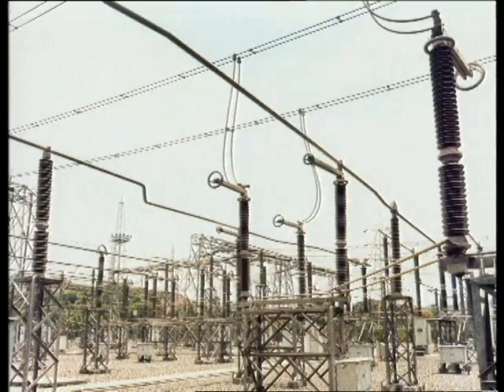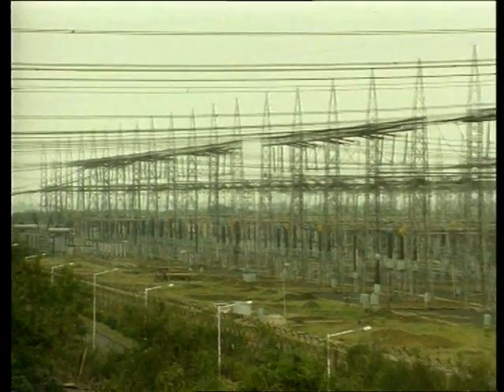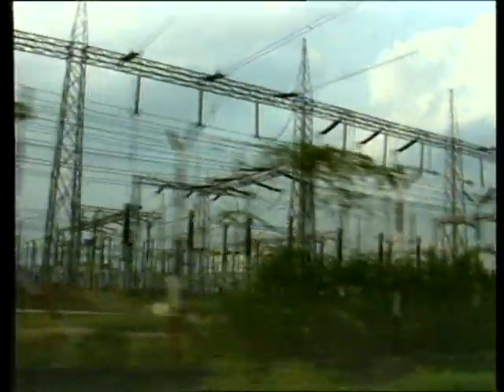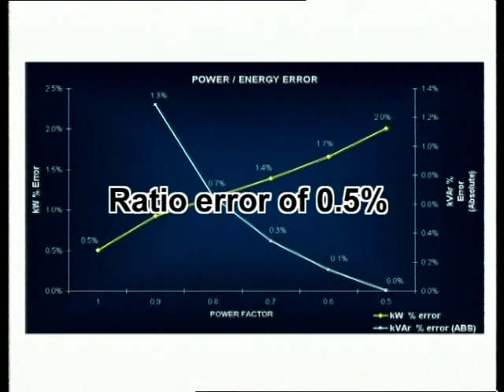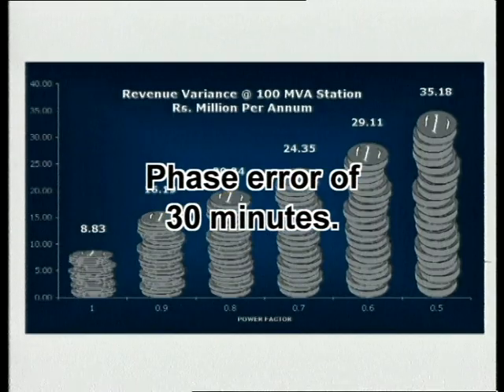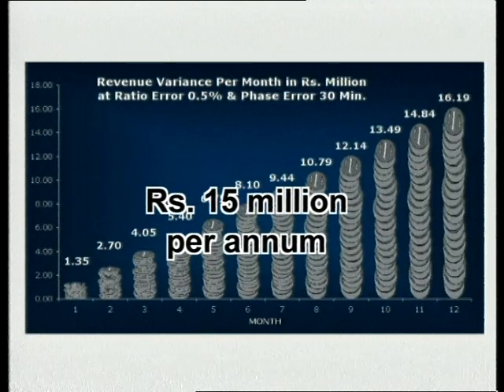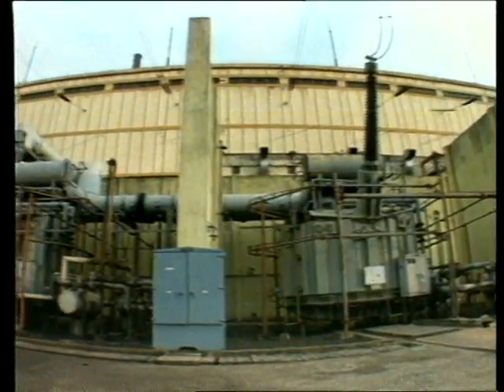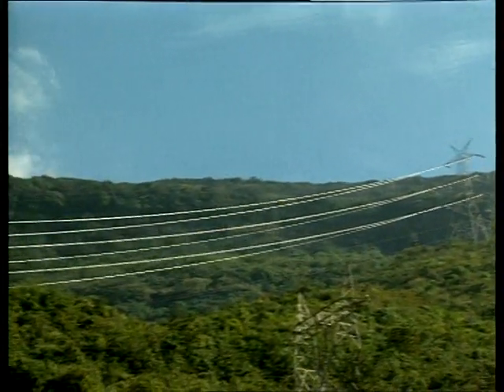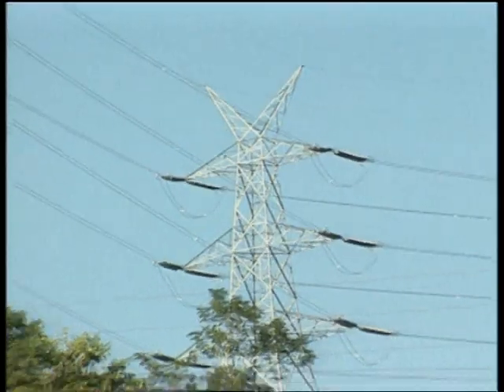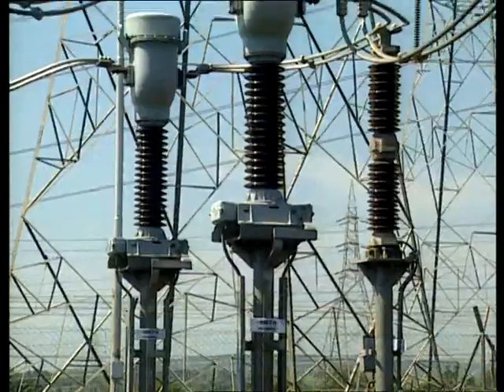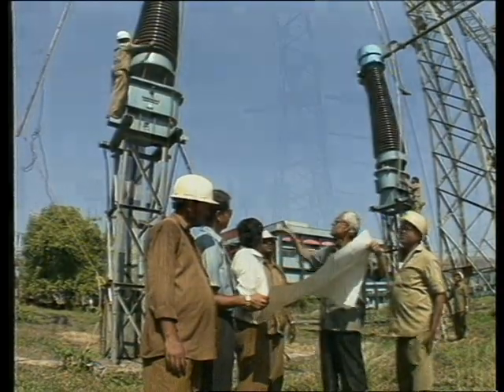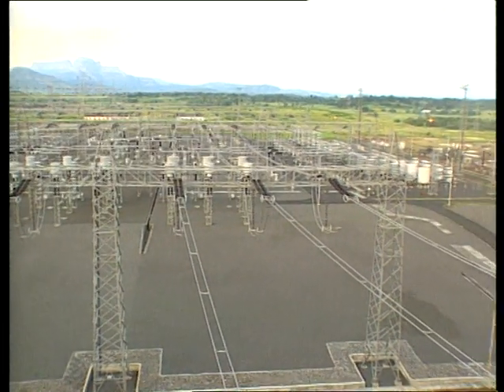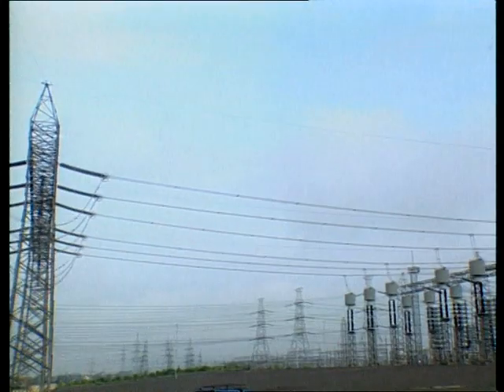However, the instrument transformers which feed the energy meters are a major contributor to the accuracy of the energy metering system. For example, a ratio error of a mere 0.5% and a phase error of just 30 minutes can cause a staggering variance of 15 million rupees per annum for a typical 100 MVA substation. Demanding system conditions, adverse climatic environments, aging, excessive burden, line faults and surges affect instrument transformer accuracy over a period of time. The sheer physical size of the current and voltage transformers make them impractical to remove and send to a distant lab for routine calibration.